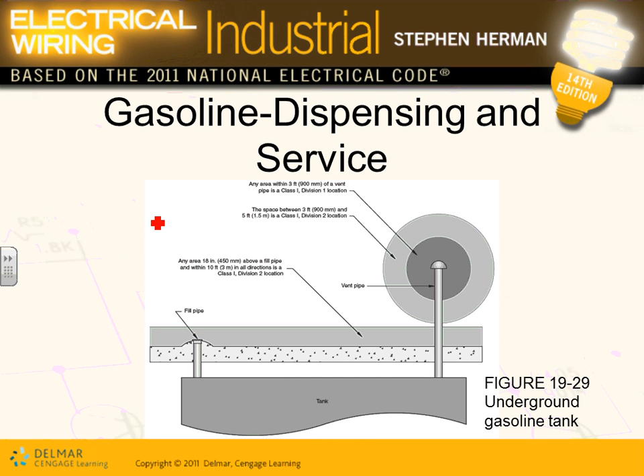Okay, same thing for an underground gasoline tank. If you have an underground gasoline tank, guys, look at this. The first 3 feet around the vent, remember they have to vent them, that area here is called class 1 div 1. And then from here to here, the next 5 feet, which is basically another circle around there, this area is class 1 div 2. So when you put your equipment, avoid putting any equipment 5 feet around that vent because it's a classified area. Same thing here, 18 inches, 10 feet away from the vent, this area is a class 1 div 2.